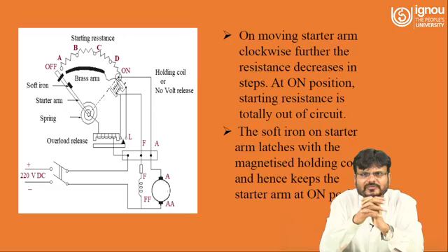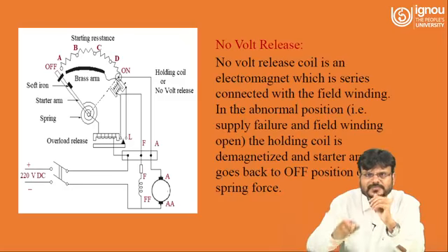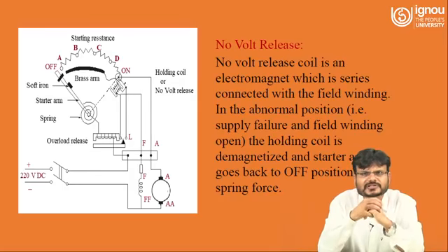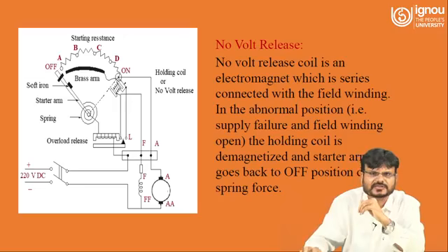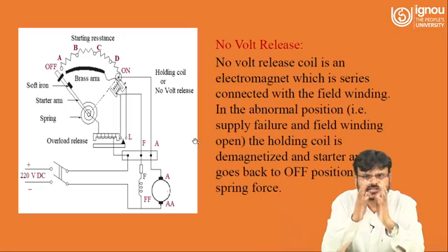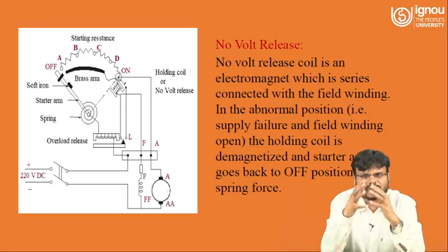Now we have to understand what is the function of this no volt release coil. This one is called no volt release coil, or you can say holding coil. No volt release coil is an electromagnet, as I already told you, which is connected in series with the field winding.